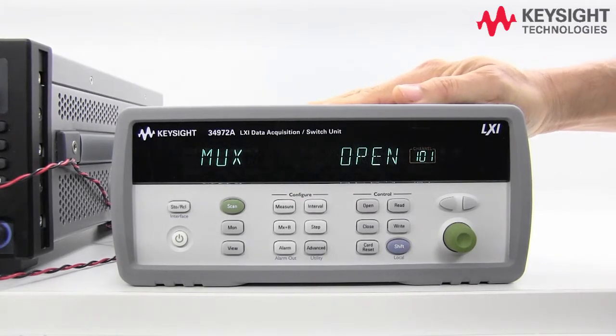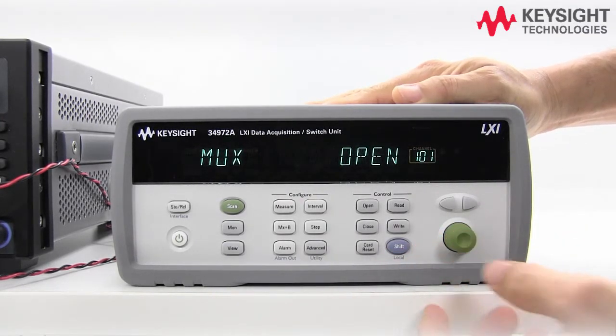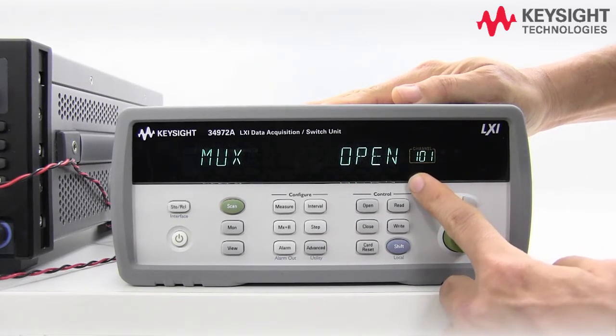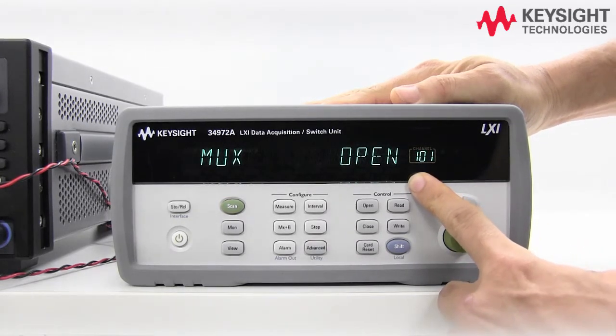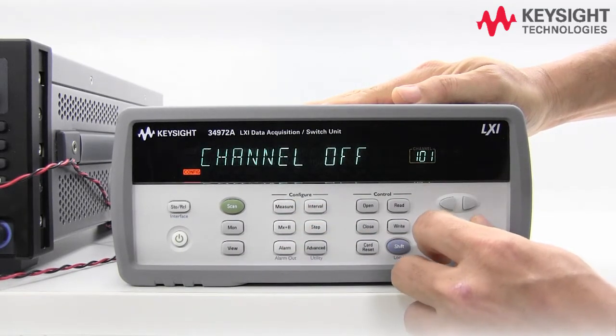Now let's go ahead and configure our DAQ. Go to channel 101 — you see that you have a 1 at the front, which means the module is in slot 1. Press measure and select DC voltage.